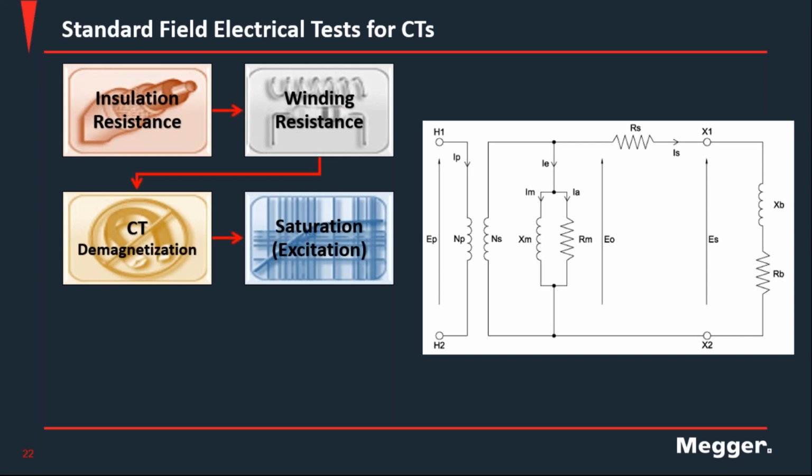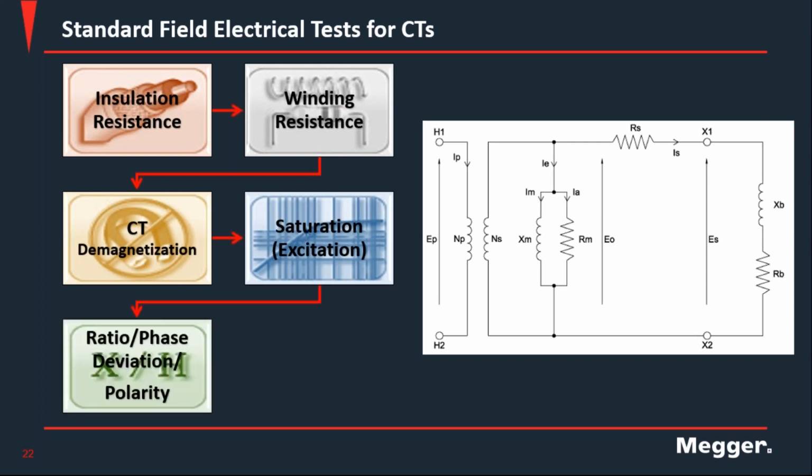The ratio correction factor gets out of the limits. So that characteristic is gathered through these tests, and that point where it starts saturating is called an knee point, and from that point on, the current will increase very fast, very rapidly as you increase the voltage. So around every 10% of voltage increase will increase the current 50%, to a point that it will be linear again, saturated, and won't increase anymore. I have results that I'm going to show on this.